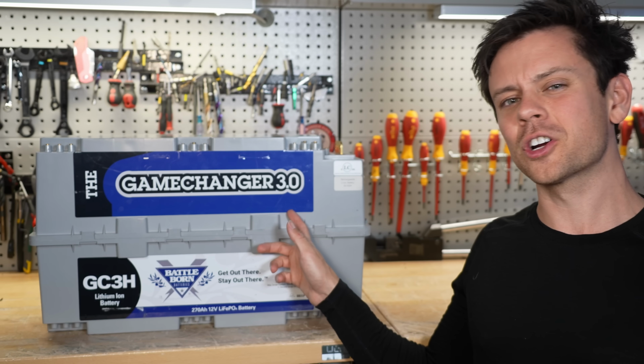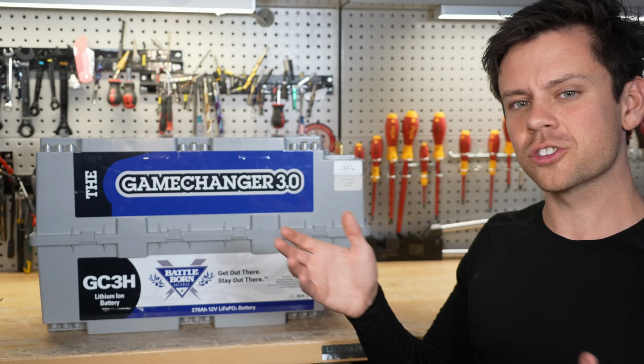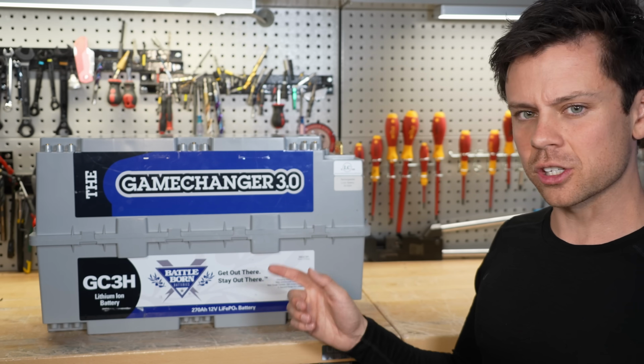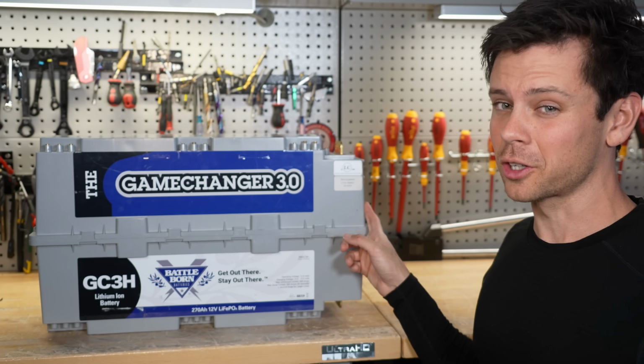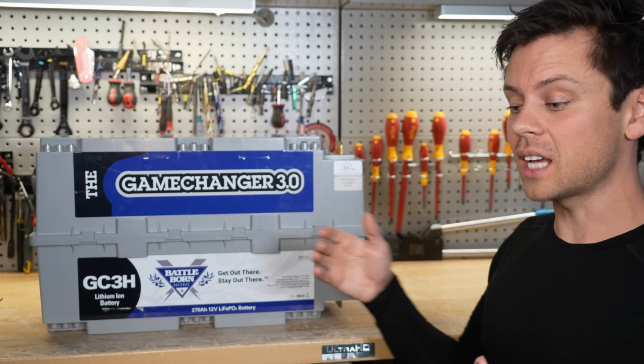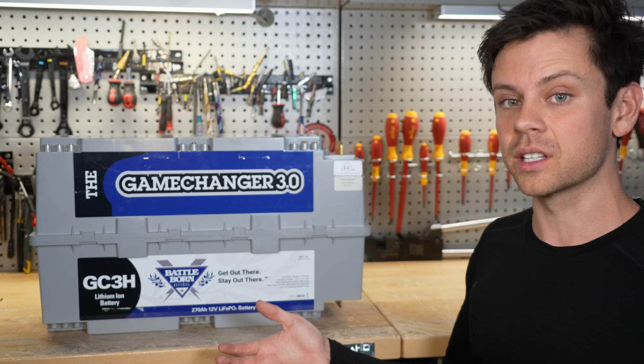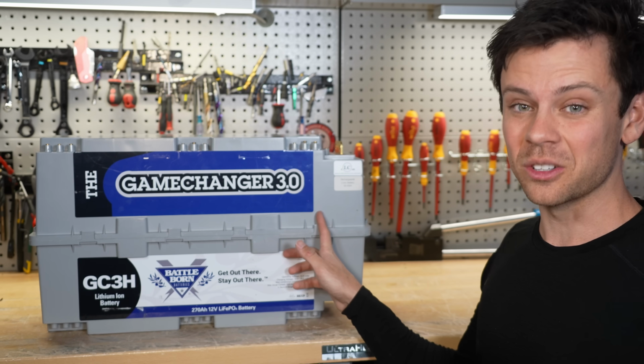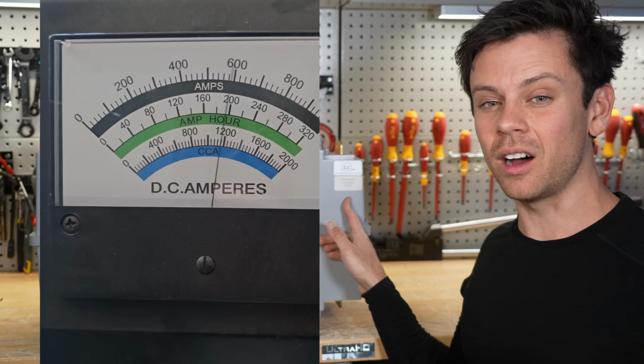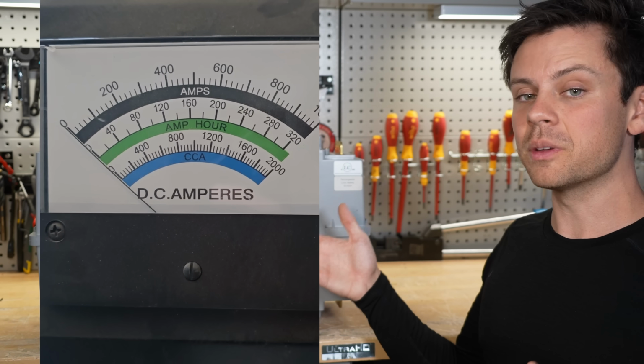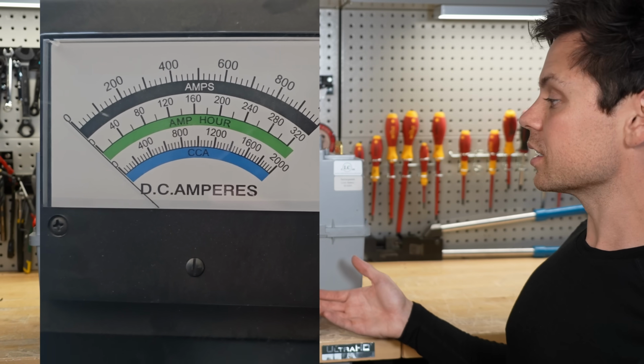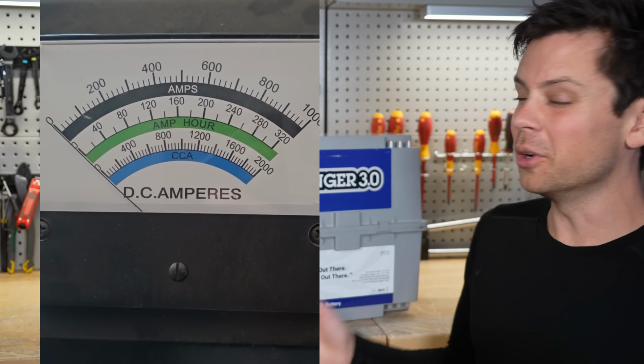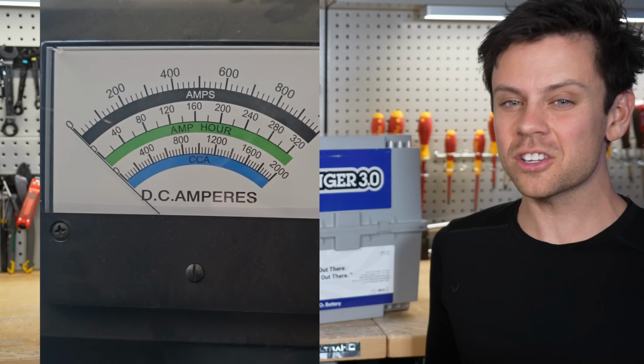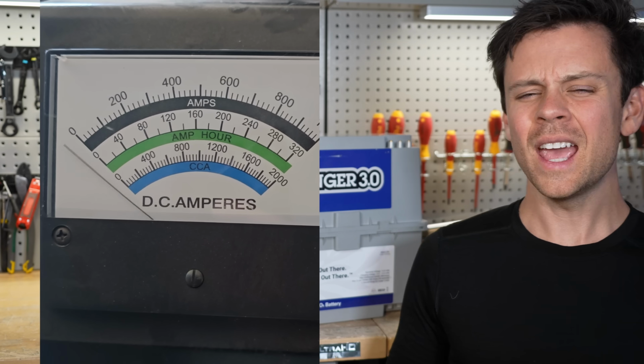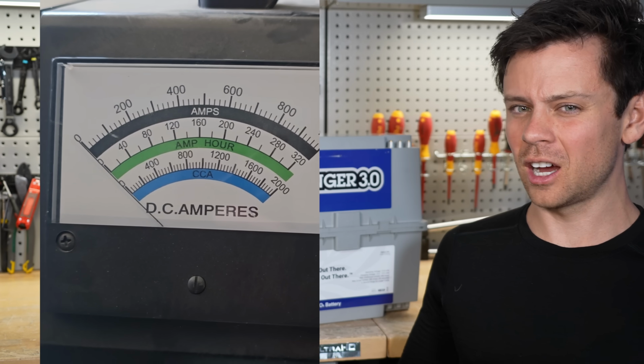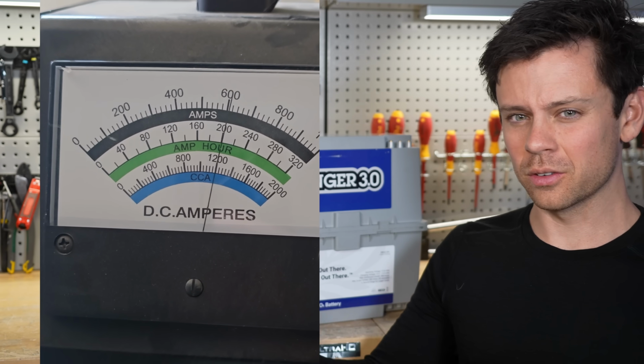Next I tested the overcurrent protection, and I pulled around 500 to 600 amps, but there was an issue. Usually if a battery shuts down from overcurrent, it stays shut down, tests to see if the load is gone, and then turns itself back on. This one does not do that. It would turn on and off, and here's a video of the needle moving back and forth, continuing to do this, which is not what you want to see. On most batteries I test, it shuts down and stays shut down until the load is gone, and even on starter battery types there's a longer time delay. This one just kept trying over and over.